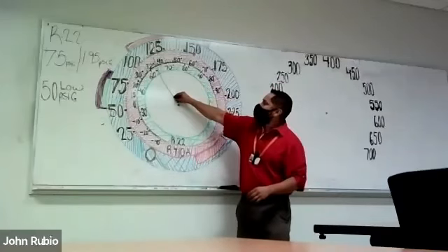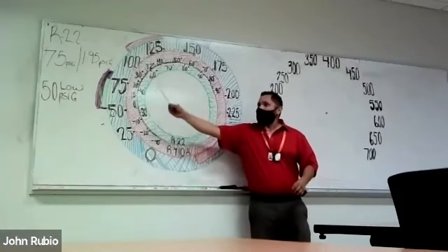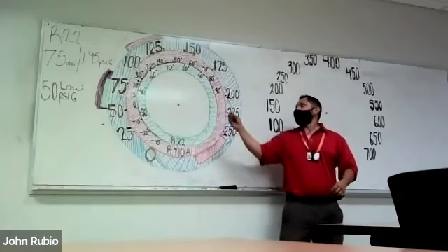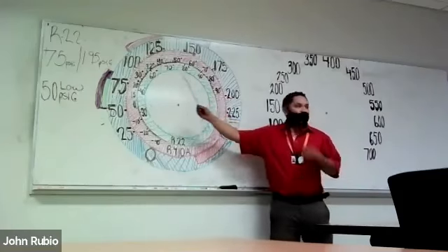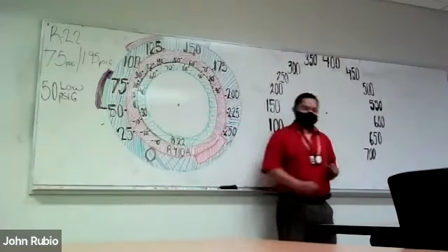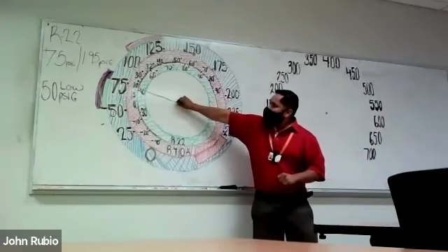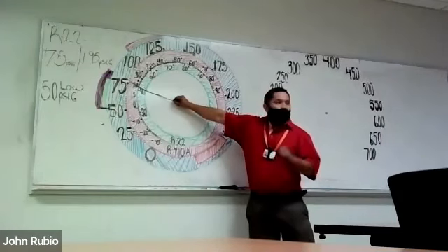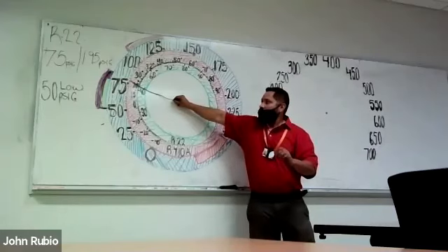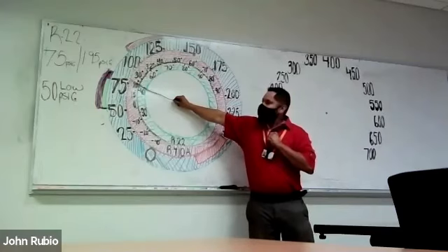When we have our refrigerant gauges, we have gauge pressure on the outside, PSIG, and then in the bars, our pink bar is our temperature. In our green bar is our temperature for the specific refrigerant. Meaning, let's look at this. When I'm R22, about 75 PSIG, follow my needle down. Where do I land in my green bar? I'm slightly above 40. I'm about 41, 42 degrees when I'm at 75 PSIG for R22.